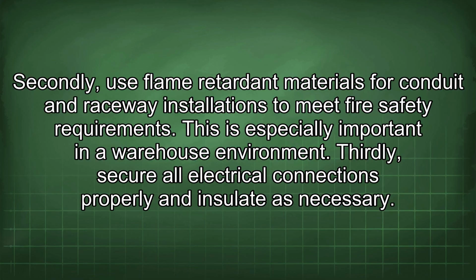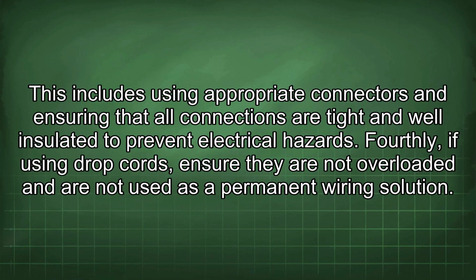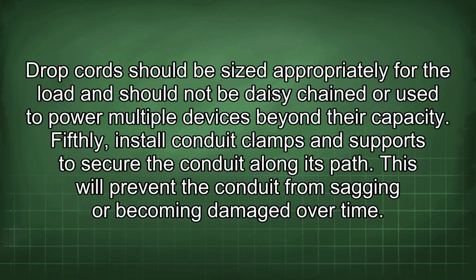Thirdly, secure all electrical connections properly and insulate as necessary. This includes using appropriate connectors and ensuring that all connections are tight and well insulated to prevent electrical hazards. Fourthly, if using drop cords, ensure they are not overloaded and are not used as a permanent wiring solution. Drop cords should be sized appropriately for the load and should not be daisy-chained or used to power multiple devices beyond their capacity. Fifthly, install conduit clamps and supports to secure the conduit along its path. This will prevent the conduit from sagging or becoming damaged over time.